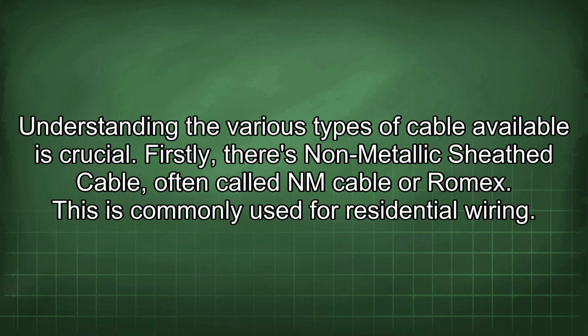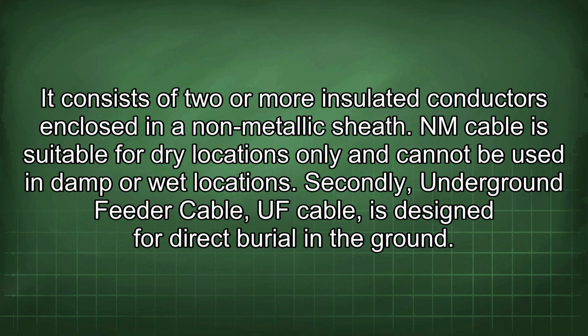Understanding the various types of cable available is crucial. Firstly, there's non-metallic sheathed cable, often called NM cable or Romex. This is commonly used for residential wiring. It consists of 2 or more insulated conductors enclosed in a non-metallic sheath. NM cable is suitable for dry locations only and cannot be used in damp or wet locations.